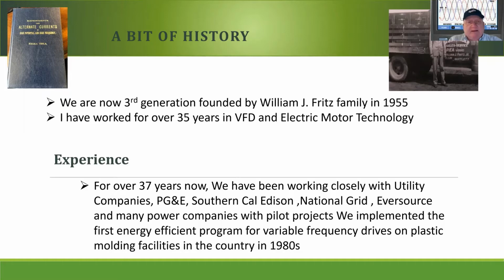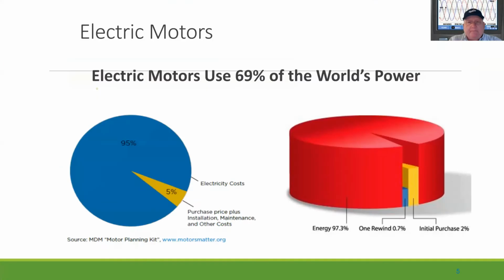I also strongly believe a lot in Mr. Tesla, and I want to show a short video next that talks about the technology we're going to talk about today. The reason is that electric motors consume 69% of our world's power, and the purchase price of the equipment, the VFDs, the pumps, the motors, all at an efficiency point, is normally about 5% of the cost, but over a 15-year period, 95% of that cost is the actual electrical power consumed to operate those pieces of equipment. So it's highly important that we get this right, because it makes massive changes in your utility cost.